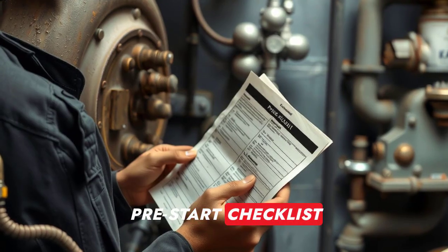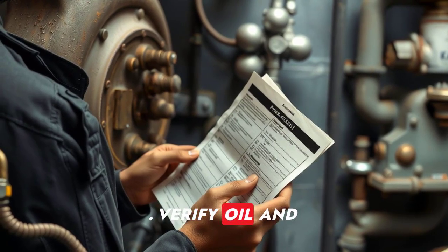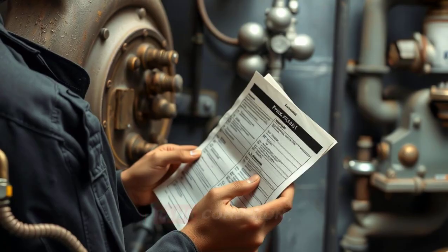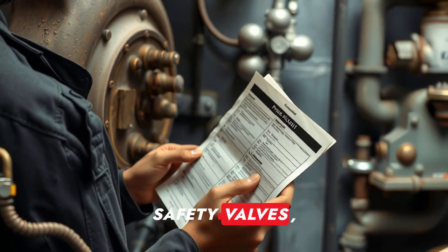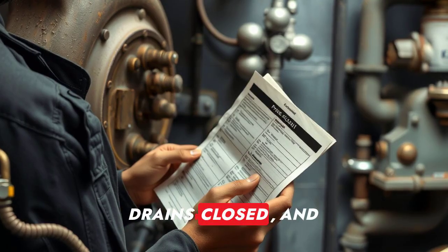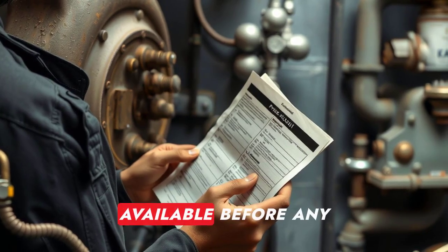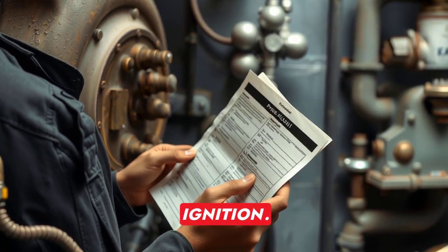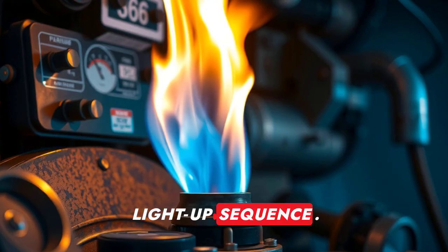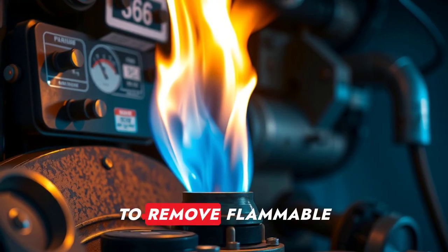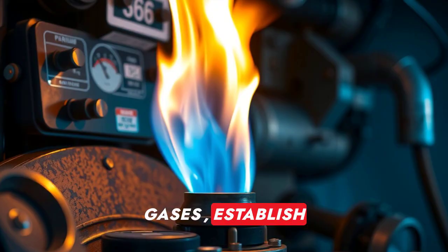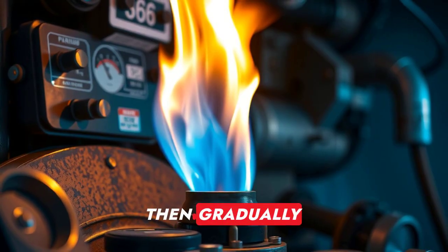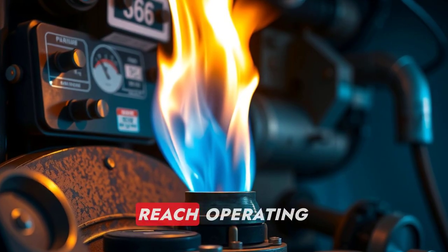Pre-start checklist. Verify oil and water levels, feed tank condition, safety valves, drains closed, and control power available before any ignition. Light up sequence. Purge the furnace to remove flammable gases, establish stable combustion, then gradually increase firing to reach operating pressure.